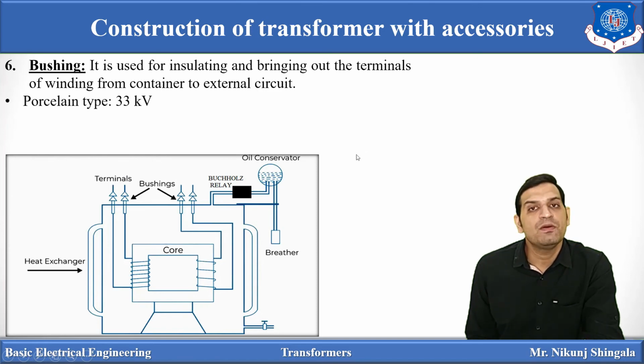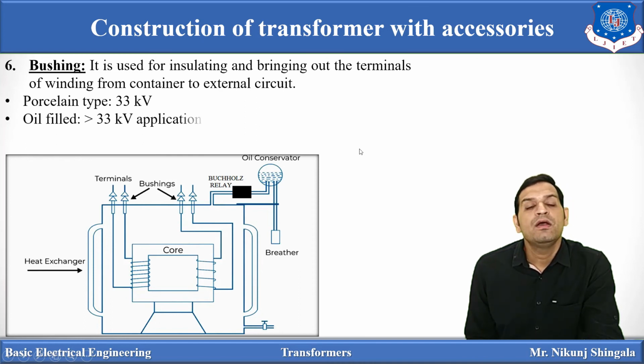There are two types of bushing: porcelain type, which is basically used up to 33 kilovolt application, and oil filled type bushings, which are used in applications greater than 33 kV.